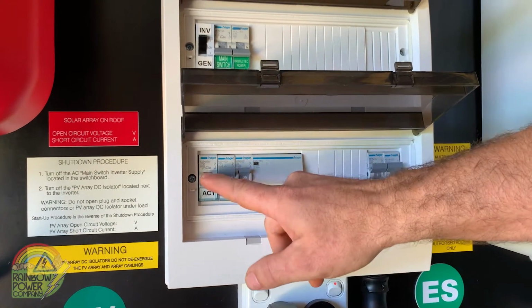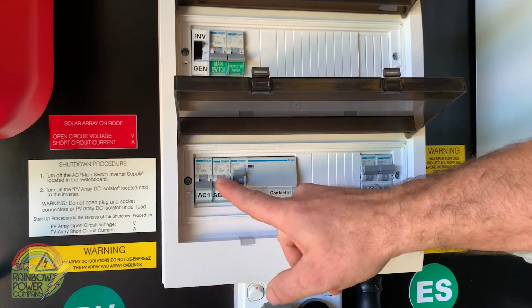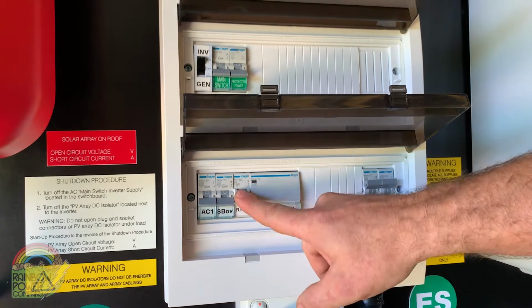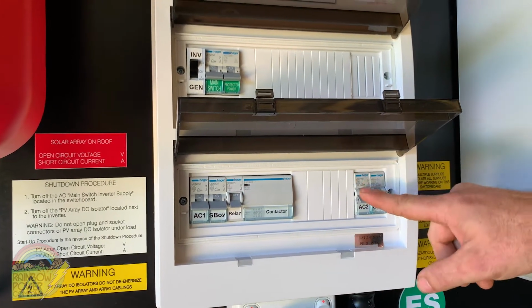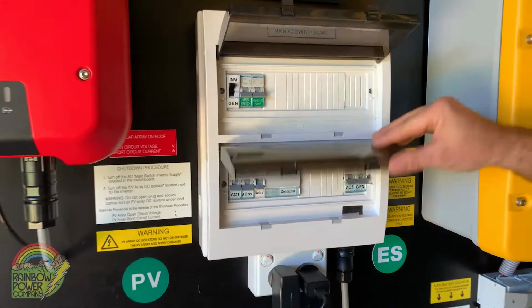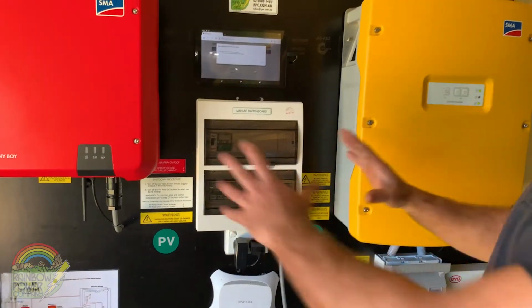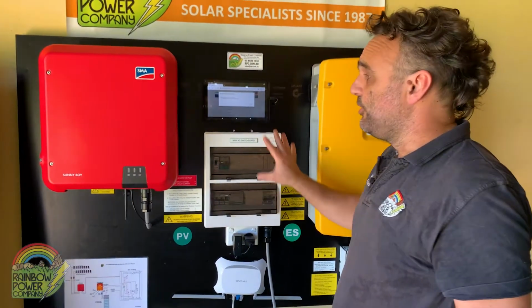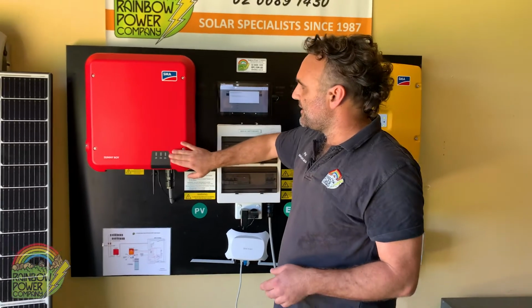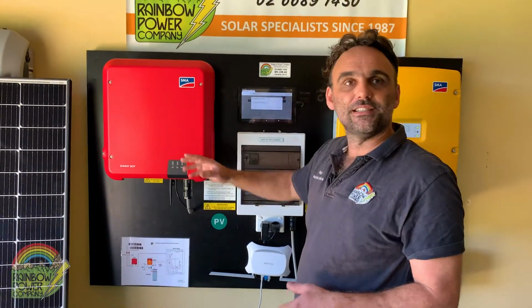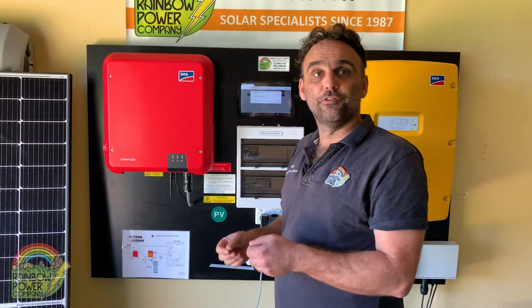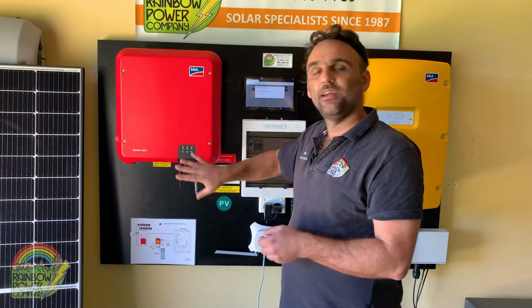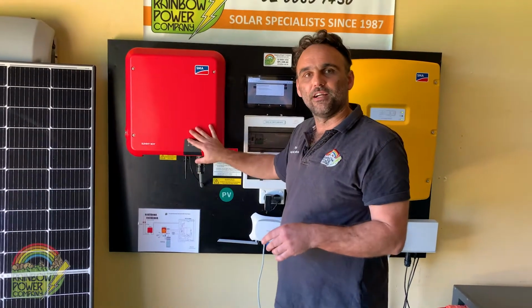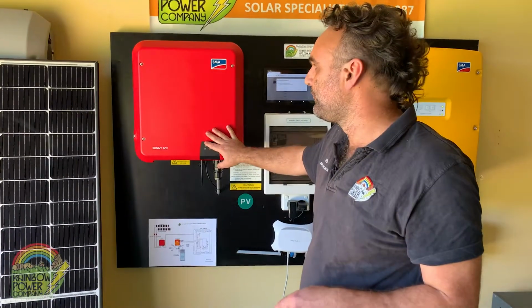So we're turning off the Sunny Island inverter. We're turning off the Sunny Boy, which is our solar inverter, the relay, and these are our generator switches coming in. We've now stopped 240 volt electricity moving around in the system, and you'll find the solar inverter will have a red light indicating a fault because it can't detect 240 volt electricity in the system anymore. That's perfectly okay - this will rectify itself once you turn the system back on.